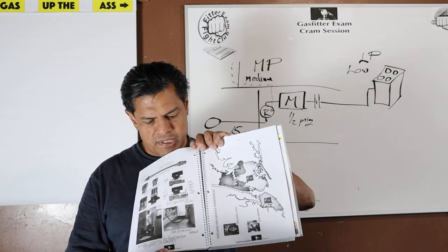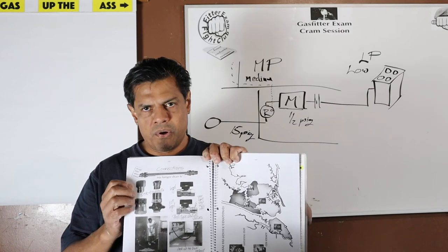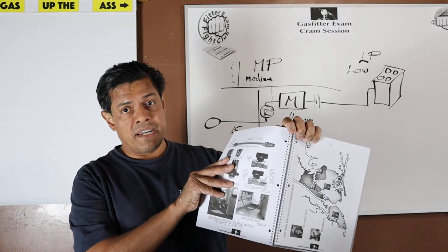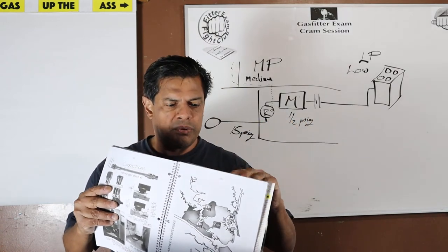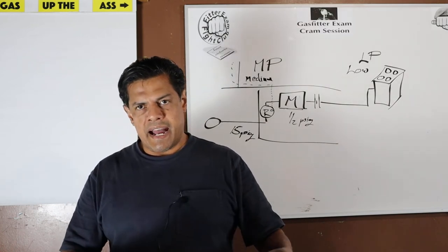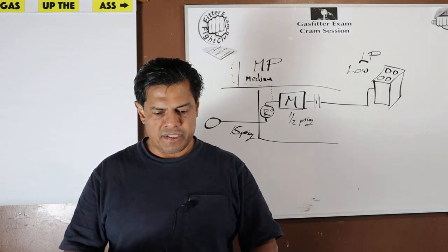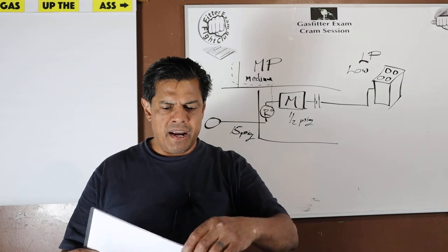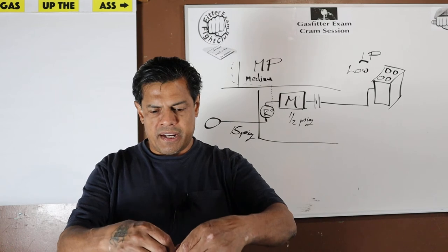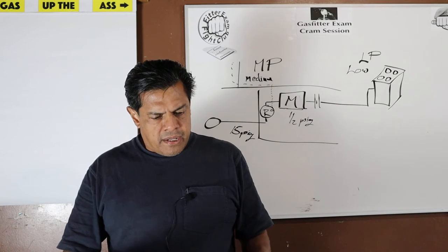Page 102, you're going to see at the top your flexible connector, no more than 6 feet, okay? It's just fancy wording. We call it flexies, but they like to say semi-rigid flexible appliance connector. Of course, it's going to be metallic. We're not allowed plastic. The only place we're allowed plastic is outside, underground. That's it. Otherwise, no plastic. And if it's outside and underground, that's not our problem anymore because anything outside, underground falls to who? The utility. It's their problem now.